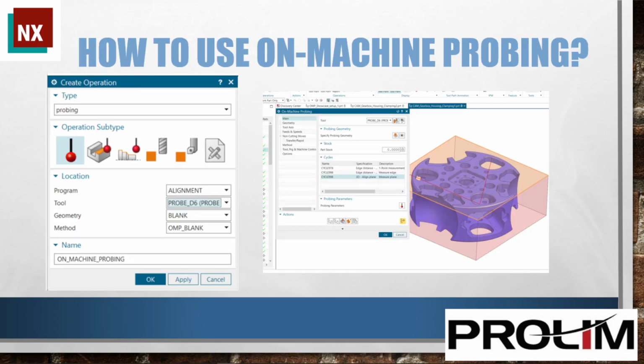So how to use OnMachine probing? A whole range of cycles are provided for the programmer. But unlike what you might expect, the programmer does not have to select the cycle and then select the geometry. Instead, the user gets a suggestion after selecting the geometry as to which cycle would be best suited for that selected feature. So based on the defined geometry, possible measuring cycles are then suggested, and the operator only has to adjust the parameters they would like to use if they're different from the default settings. So let's take a look at this module.